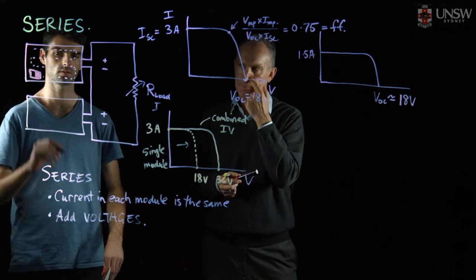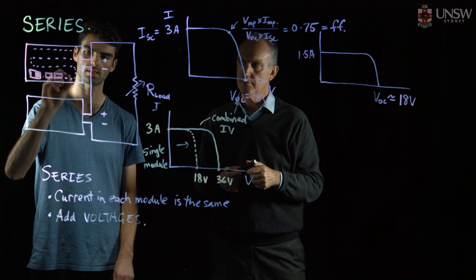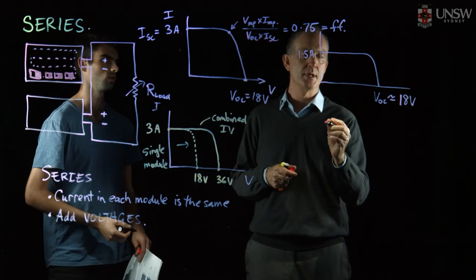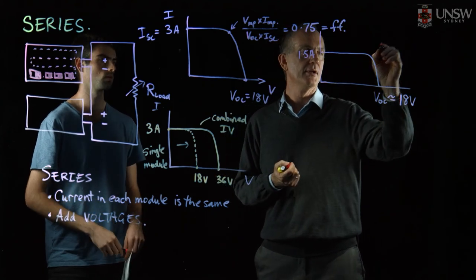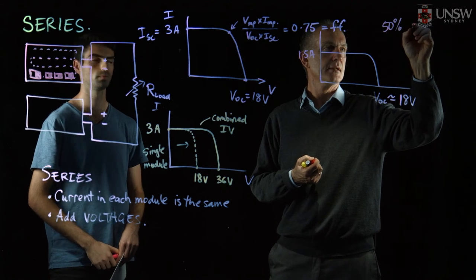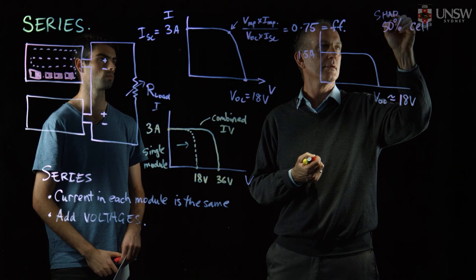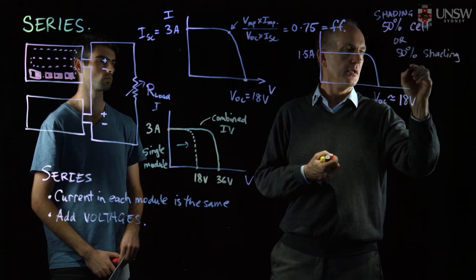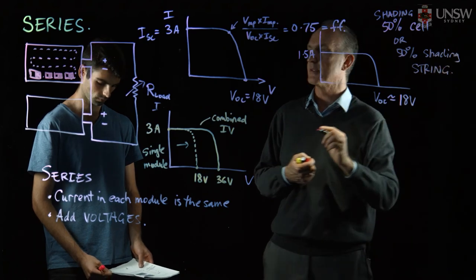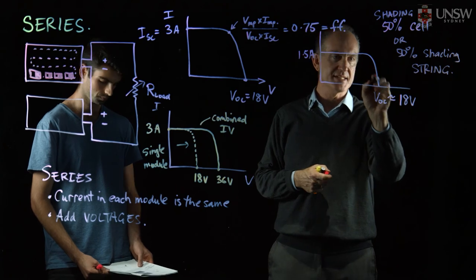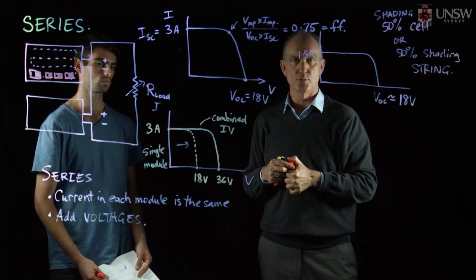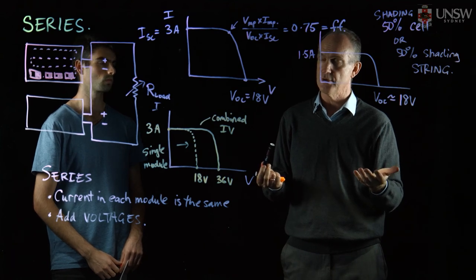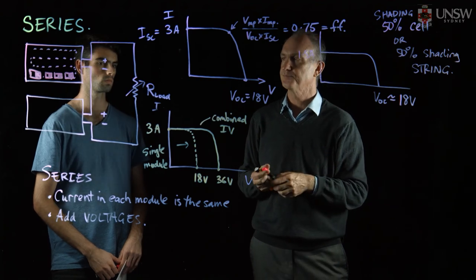If an entire row of cells in the module is shaded by 50%, how would that affect the curve? If 50% shading covers a whole string of cells connected together, that string is shaded by 50%, reducing the current by half for the whole string. Because the rest of the cells in the module are connected in series, the whole module output is reduced by 50%.